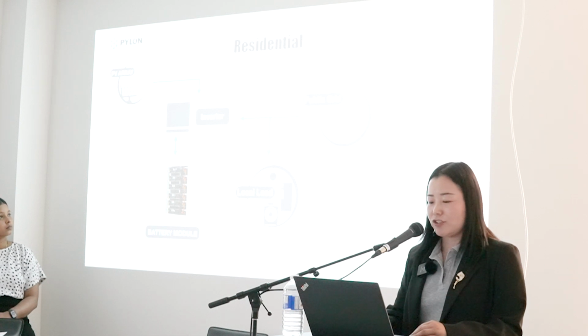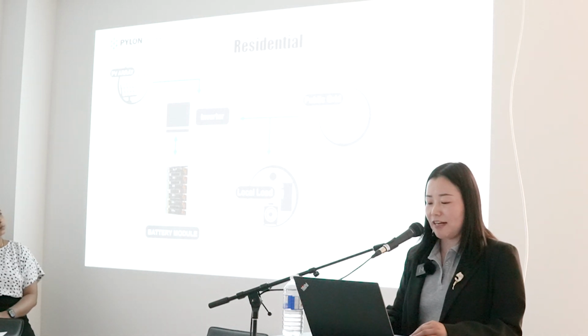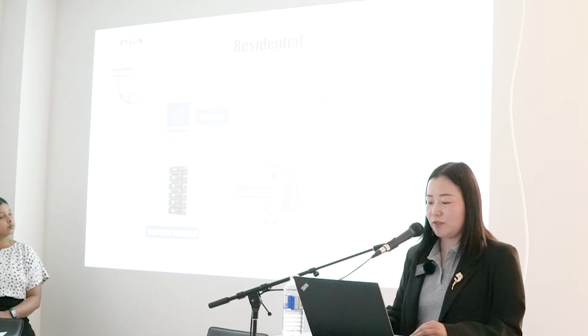Secondly, you can do peak shaving conditions. The grid could charge the battery when the electricity fee is low. Then the battery provides power to loads when the electricity fee is high. Thirdly, the self-use mode. At sunny day, PV array could provide power to load. If PV still have power, it could charge batteries. When the batteries are fully charged and the PV still have power, it could feed back to the grid.